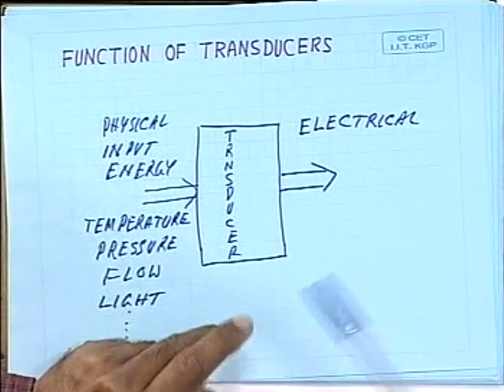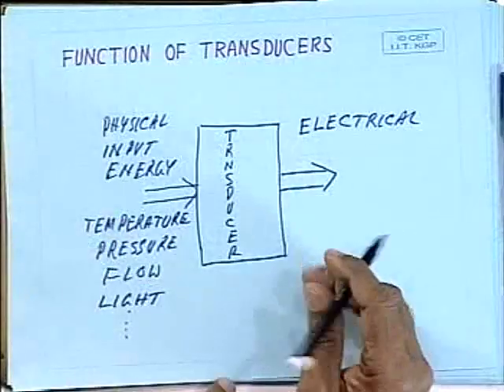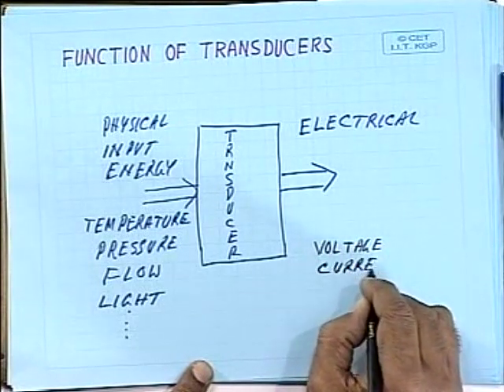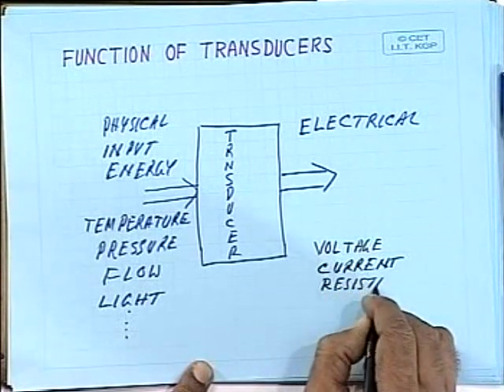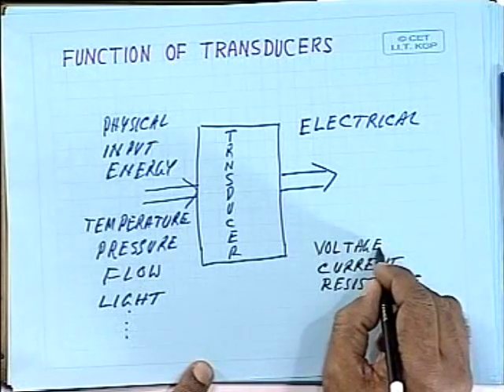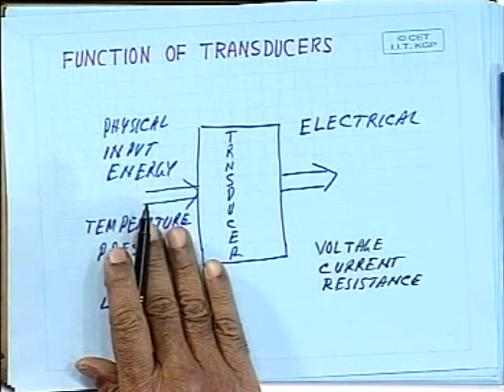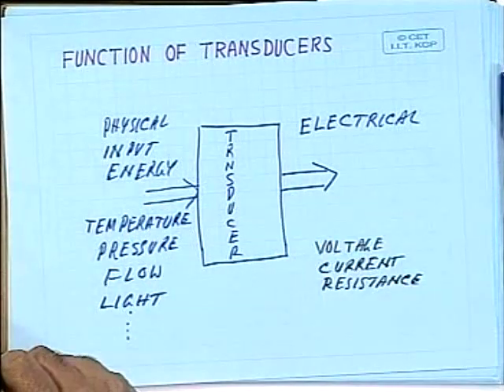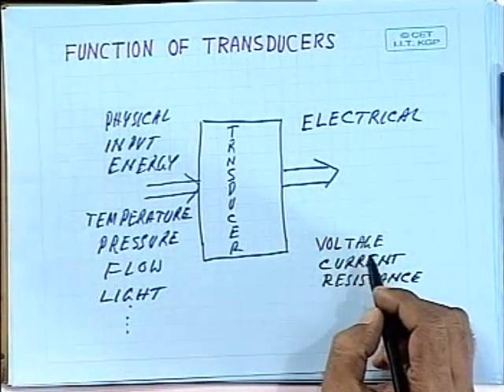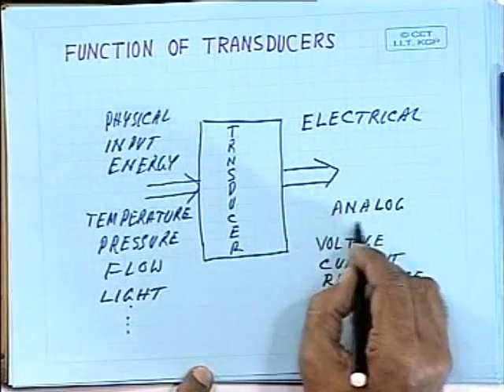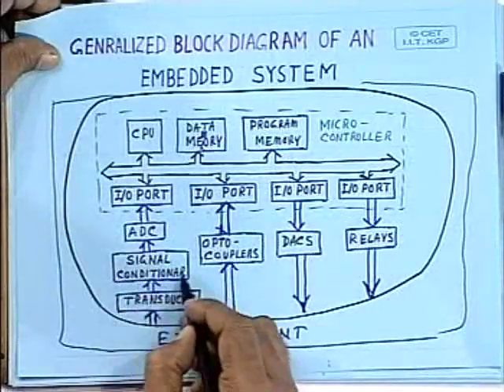The electrical parameters are essentially resistance, voltage, and current. So the transducer will produce voltage, current, or a resistance that changes according to the physical parameters. The transducer converts physical energy to electrical energy. These signals will usually be analog in nature and of very low strength, so you will require a signal conditioner to interface with the transducer, and the analog output is then converted to digital form with the help of an ADC.